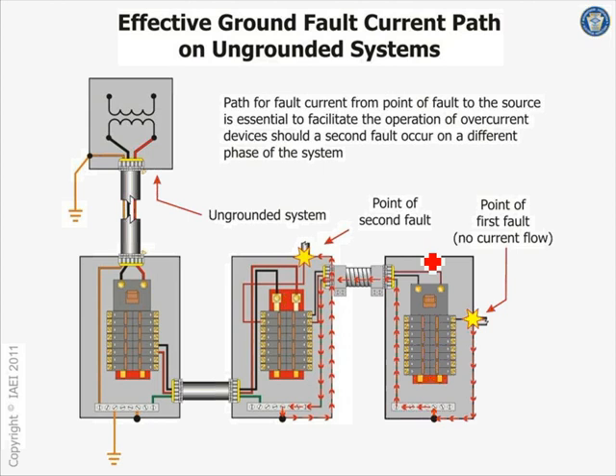Typically, guys, an ungrounded system, I have never seen a building service that's an ungrounded system. Anybody have seen an ungrounded power system feeding a building? An ungrounded system is typically created inside the building. You go to the assembly line where they bring power in, and what they do is they have a transformer here, ungrounded, and they feed all this assembly line equipment from that transformer. So when you get the first ground fault, you're still standing. If you get a second ground fault on a second phase, you drop.